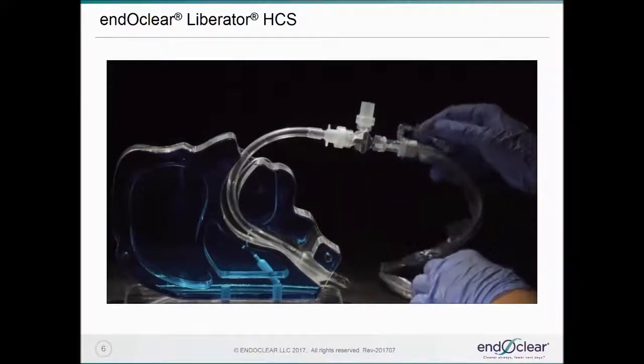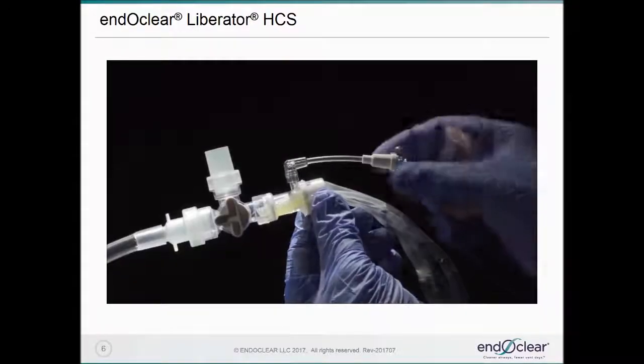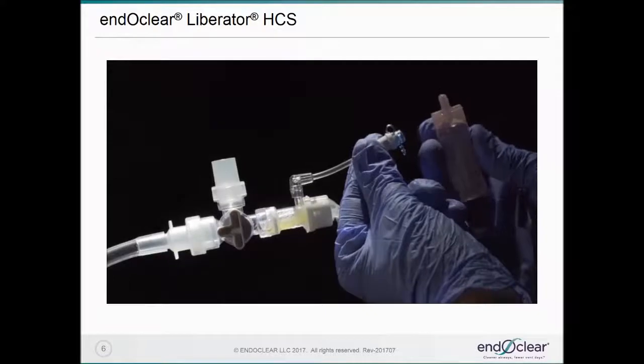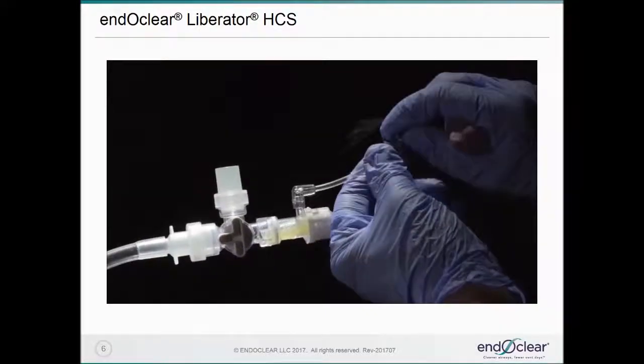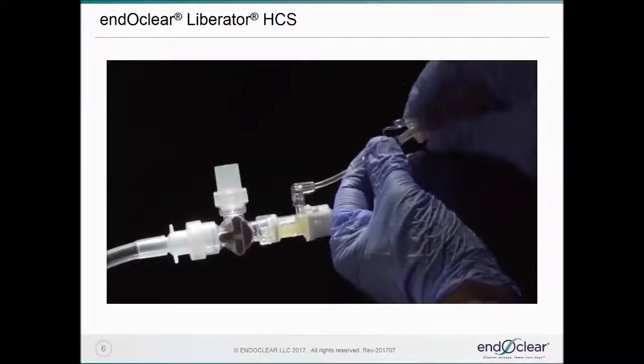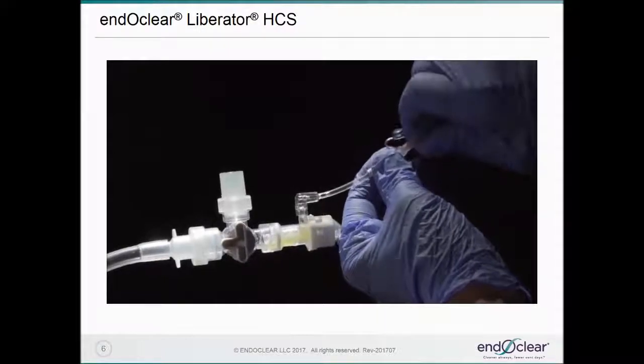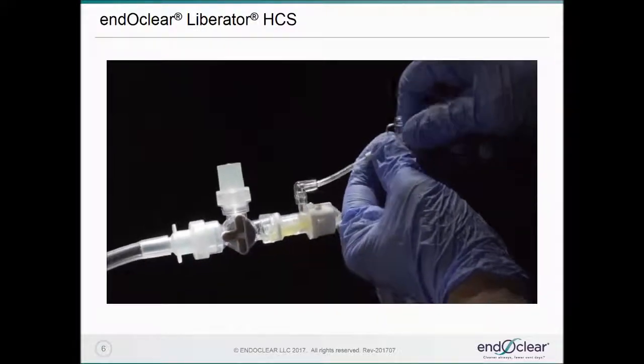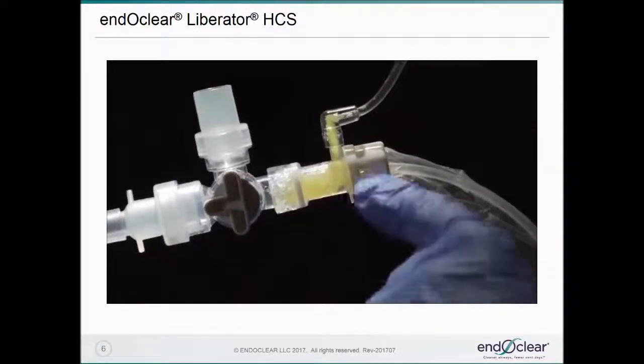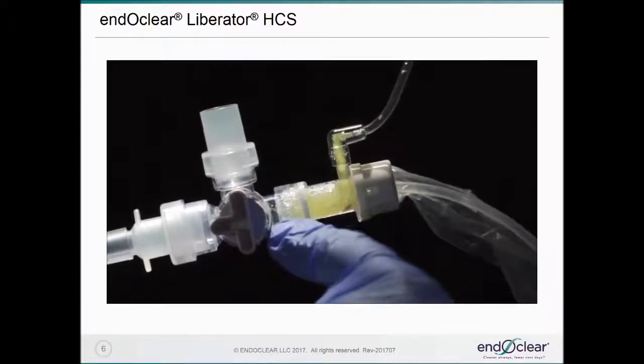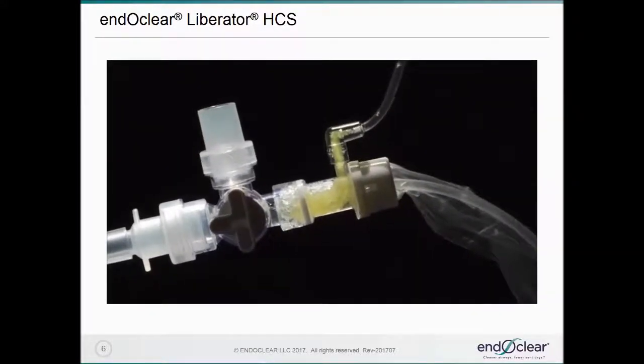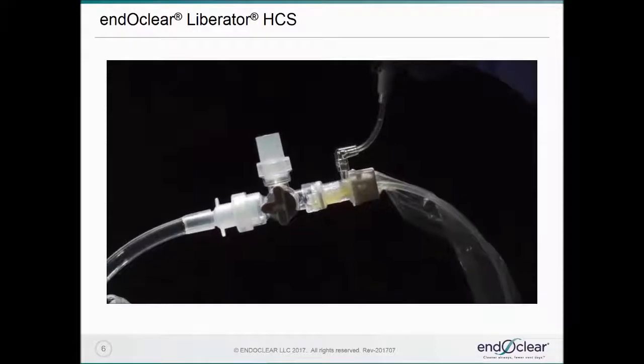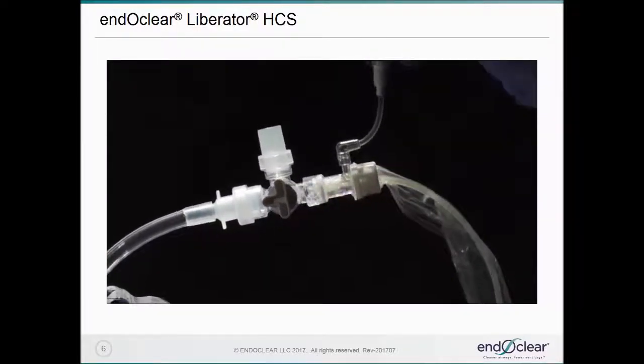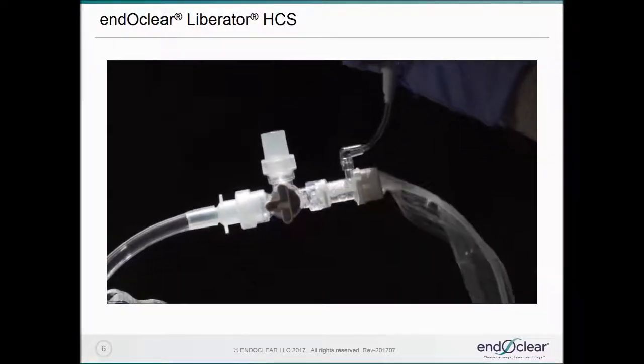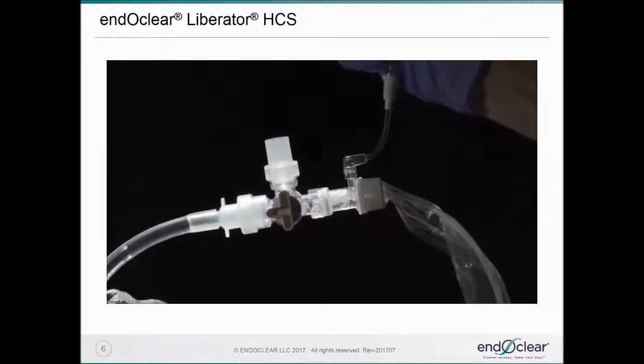Now I'm going to close the manifold, and a 15 cc saline bullet is connected to the injection port of the cleaning chamber. We elevate it a bit so that the cleaning chamber is in a downward direction towards the suction holes in the catheter. And then as we apply suction to the cleaning chamber, we flush the cleaning chamber with saline.